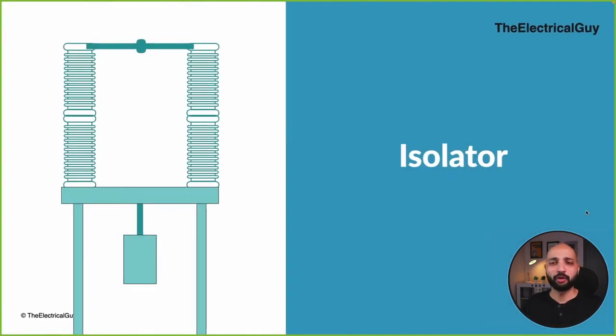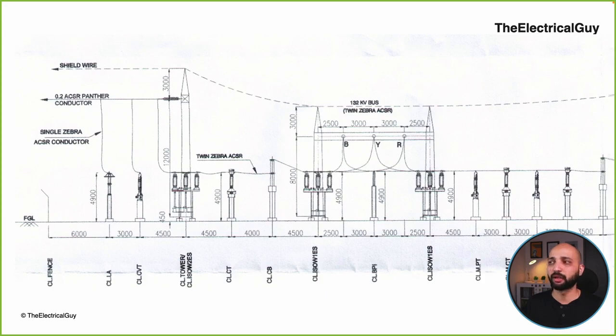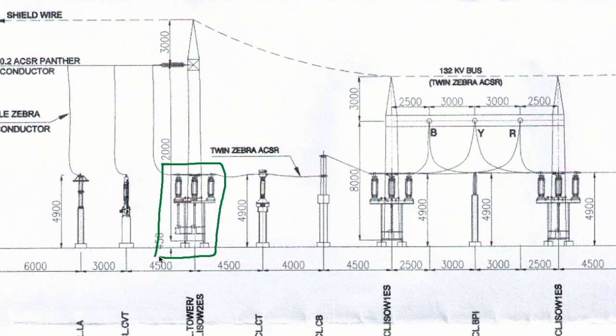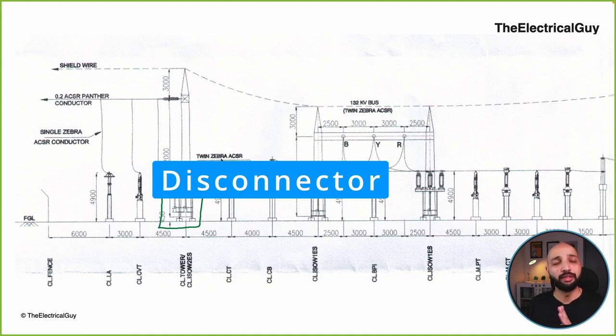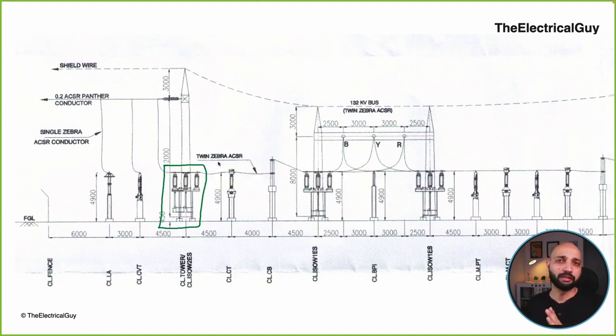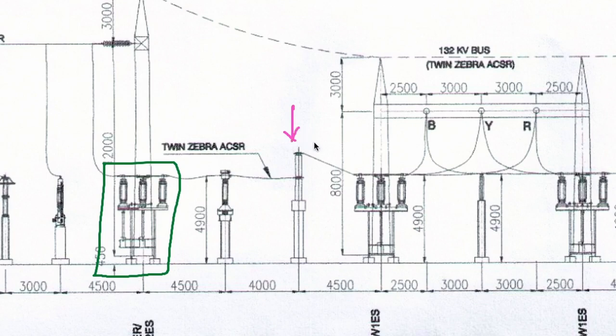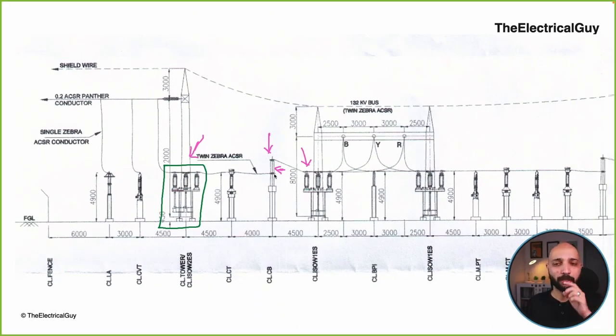Now moving on, let's talk about the next device that we have, and that is the isolator. This device right here you can see is an isolator, or it is also called a disconnector. The function of an isolator or disconnector is to disconnect a particular part in the substation, which allows maintenance to be carried out on it. So for example, let's say I want to carry out maintenance on this particular circuit breaker. I will first open the circuit breaker, then open these two disconnectors right here, and then I can carry out maintenance on this circuit breaker without any worry, because this portion is disconnected from both ends in the system, and that is one of the applications of an isolator or disconnector.